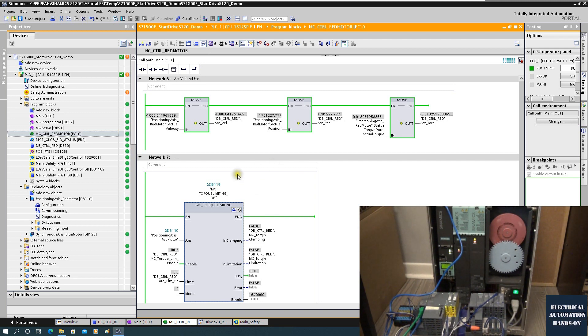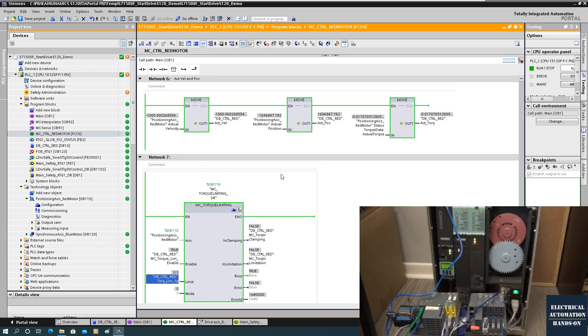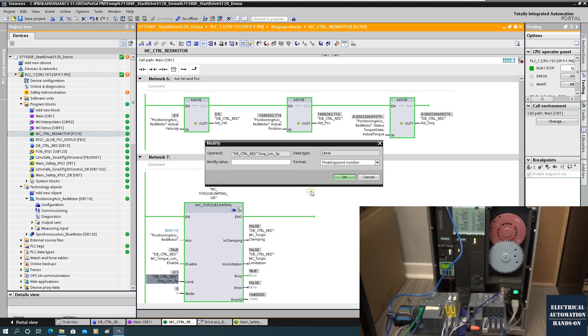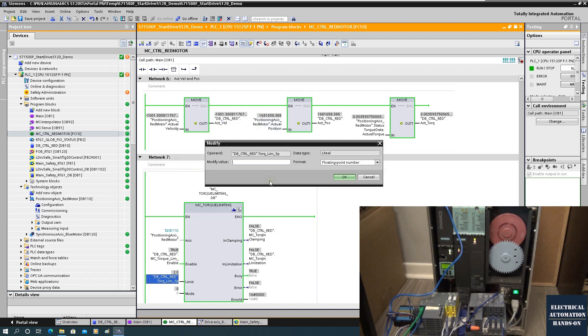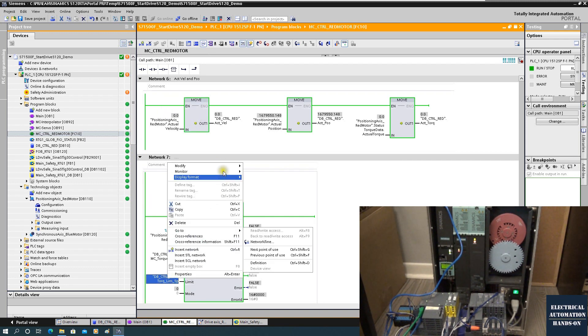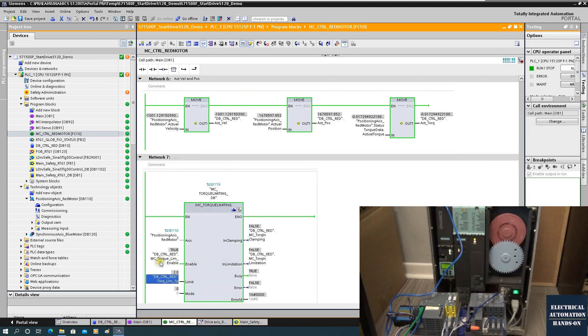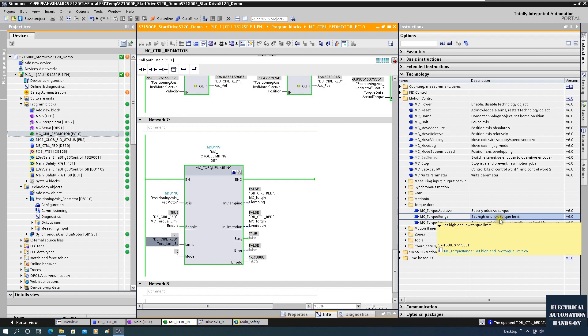Now let me do another test. Let me change this setpoint from 0.3 to minus 0.3 and see if the setpoint can be set less than zero. We will see the motor stops running because we've killed the total torque — there is no torque to drive the motor anymore. This means the setpoint cannot be set to a negative value — it cannot be less than zero. Once we change the setpoint from a negative to a positive value, the motor starts up again. So this setting cannot be less than zero.